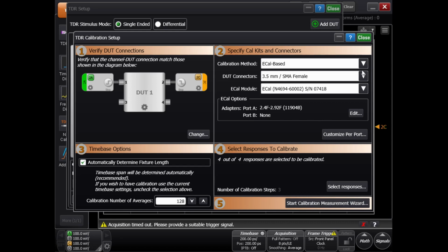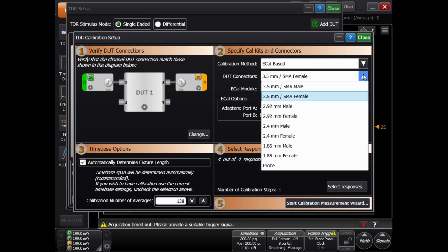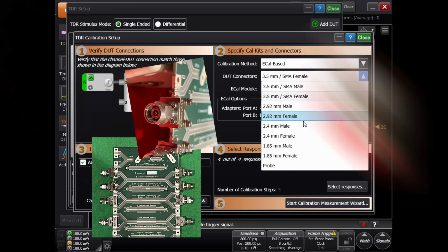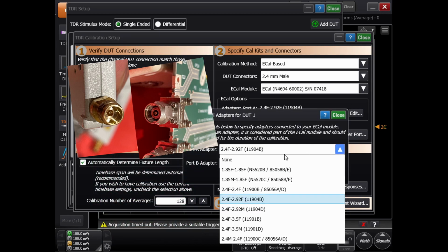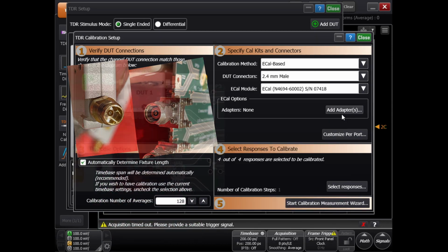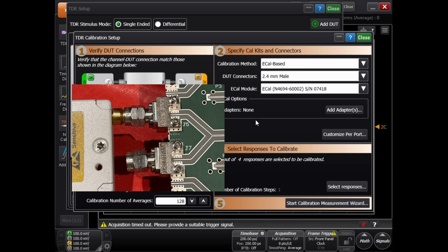I'm going to go back to the situation I had before. Remember, we have a 2.4 millimeter male on my DUT. And now I have to remove this. We put none. We don't need that anymore. And we are good to go. So we will be connecting directly to a 2.4 millimeter male DUT. And we can continue on. And then we can start the calibration.